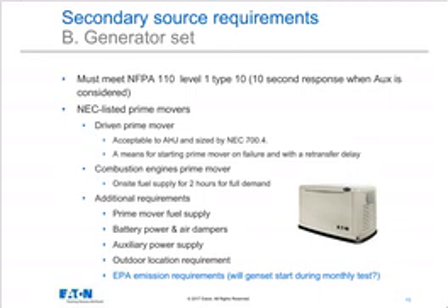So the engine must have on-site fuel supply for about 2 hours. Even though the technical requirement for backup time is 90 minutes, they still require fuel tanks either in the base of the generator or even underground for at least 2 hours of full expected demand. So the generator can run for at least 2 hours on its designated fuel. Other requirements: fuel supply for the prime mover, battery power, and air dampers.